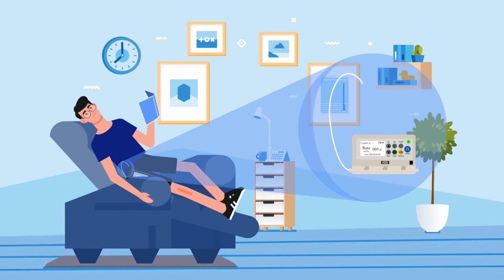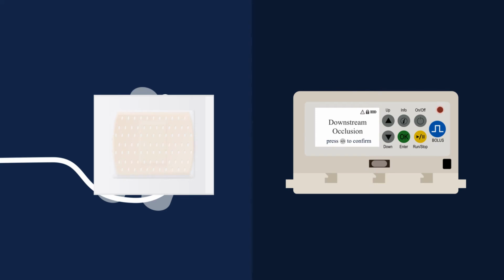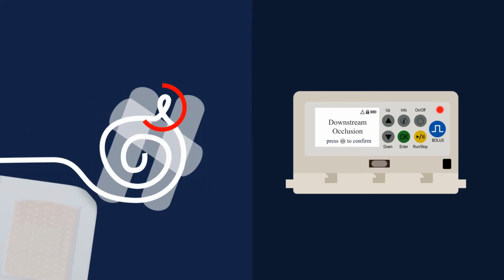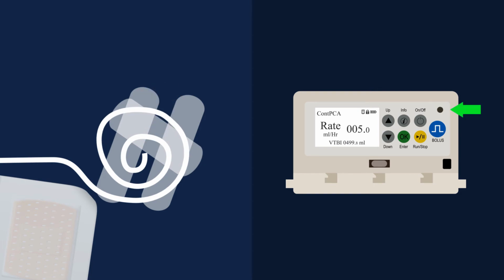more peacefully. Other times, there might actually be a bend in the catheter under the dressing or beneath the skin that's causing resistance. When the pump senses the line pressure climb, it will stop pumping, display the downstream occlusion message, and flash the red LED light while it holds the pressure in the line pushing against the blockage. If you see the red LED light turn green and the downstream occlusion message disappear from the screen, it means the pump was able to push medication through the point of resistance and automatically resume the infusion.